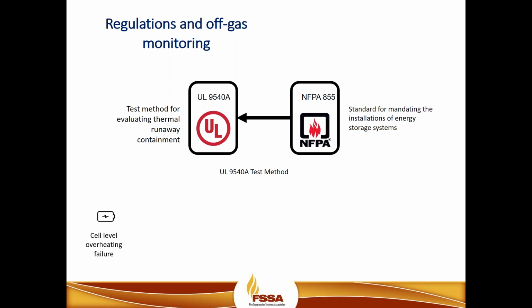NFPA 75 has introduced language into the annex looking for that electrolyte detection, off-gassing, so specific types of gases where the off-gas can be detected through early warning detection and then work in conjunction with an approved battery management system. So NFPA 75 has adopted language in the annex that talks specifically about that. And many of the committee members are looking to push that code language throughout the additional codes for the requirement of redundancy of off-gas detection.